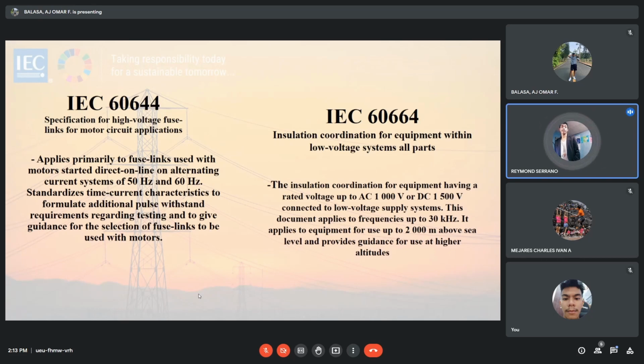It provides requirements for technical committees to determine clearances, creepage distance, and criteria for solid insulation. It includes methods of electrical testing with respect to insulation coordination. The minimum clearances specified in these documents do not apply where gases are present. Special requirements for such situations can be specified in the descriptions of the relevant technical committees.